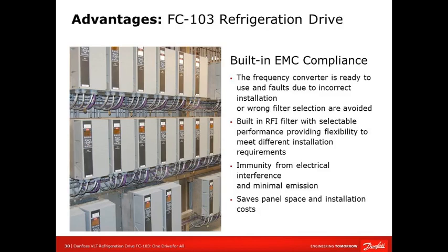What we're doing is, just from experience, we know it's just fewer components that either the panel builder or the end user has to buy to help protect against, for example, electromagnetic interference. In Europe it's maybe more commonplace, I think, because the manufacturing is located in a residential area or near a hospital, for example, whereas in the U.S. we have a little more space. But these are things that Danfoss does built in. And if you have questions about harmonics and things like that, just ask us. We have solutions for that if it's a requirement or if it's listed in the specification.